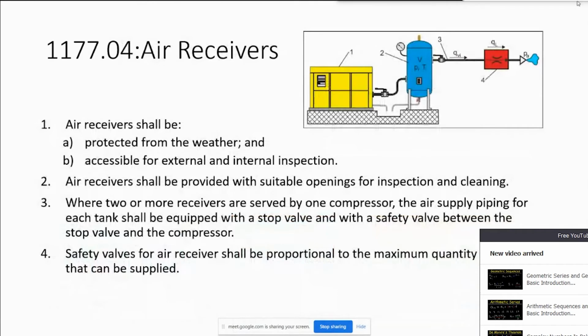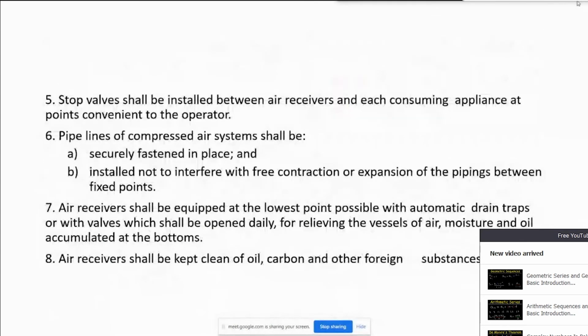Air receivers. Air receivers shall be protected from the weather and accessible for external and internal inspection. A receiver shall be provided with suitable openings for inspection and cleaning. Where two or more receivers are served by one compressor, the air supply piping for each tank shall be equipped with a stop valve and with a safety valve between the stop valve and the compressor. Safety valves for air receivers shall be proportional to the maximum quantity of free air that can be supplied. A stop valve shall be installed between a receiver and each consuming appliance at points convenient to the operator.